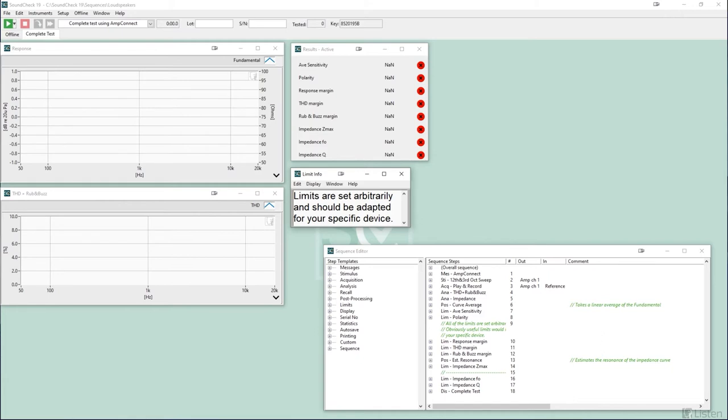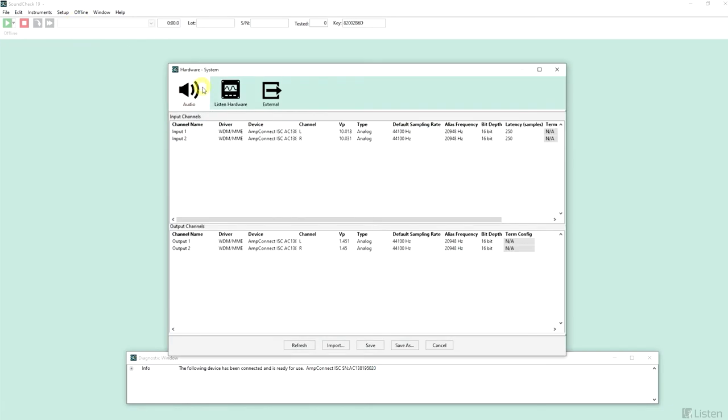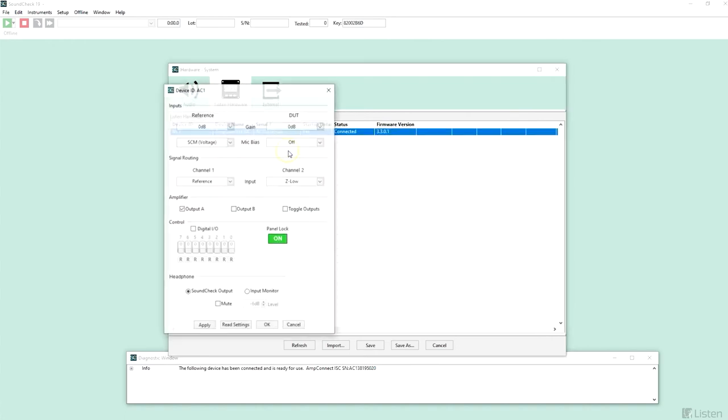While designed for end-of-line production testing, the sequence is also suitable for basic R&D testing. Today's example at my home office is far from anechoic, and the results are only intended for demonstrative purposes. First, we will check the hardware settings in the setup menu. Under the audio tab, our inputs and outputs are automatically assigned with an AmpConnect ISC, and the calibrations, settings, and VP values are auto-populated from the device, making setup a real breeze. AmpConnect ISC and other Listen hardware are true plug-and-play devices, providing full software control and auto-configuration through SoundCheck.